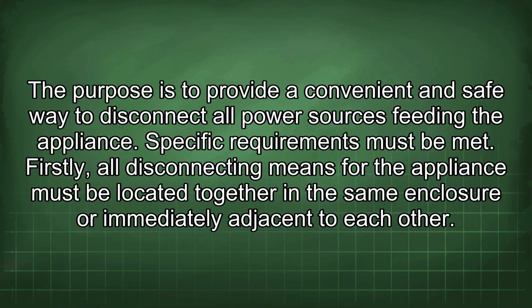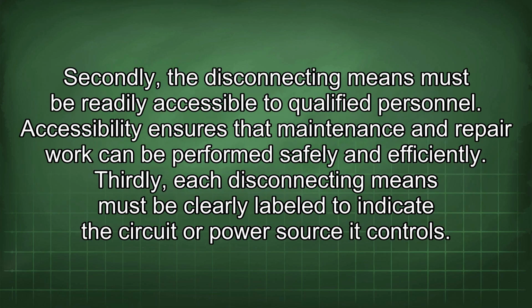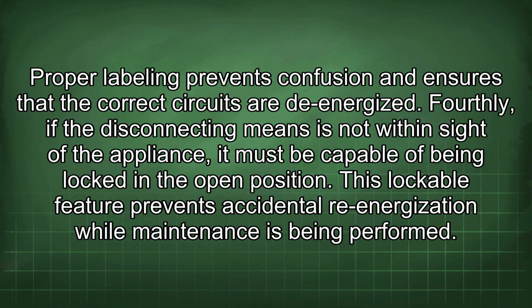Specific requirements must be met. Firstly, all disconnecting means for the appliance must be located together in the same enclosure or immediately adjacent to each other. Secondly, the disconnecting means must be readily accessible to qualified personnel. Accessibility ensures that maintenance and repair work can be performed safely and efficiently. Thirdly, each disconnecting means must be clearly labeled to indicate the circuit or power source it controls. Proper labeling prevents confusion and ensures that the correct circuits are de-energized. Fourthly, if the disconnecting means is not within sight of the appliance, it must be capable of being locked in the open position. This lockable feature prevents accidental re-energization while maintenance is being performed.